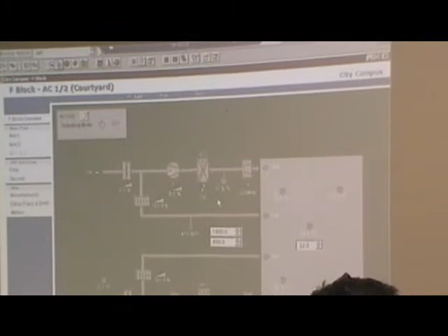We did have some issues quite recently with the compressors tripping out, and isolated that back to an initial programming error, or well, let's call it an error, because it was tripping out. So Siemens popped down and reprogrammed it for us, and this is about 3 months ago. We haven't had an issue since, touch wood. Generally speaking, this system operates pretty well. There's only been a couple of times where I've had to manually adjust the fan speed when there's been a public address, or somebody's giving a speech or a presentation, when there's a lot of people and the system's trying to cope and it's going flat out, and of course the person's trying to speak over the PA and can't really be heard. So a couple of times I've just sacrificed CO2 levels so that the presenter can be heard.